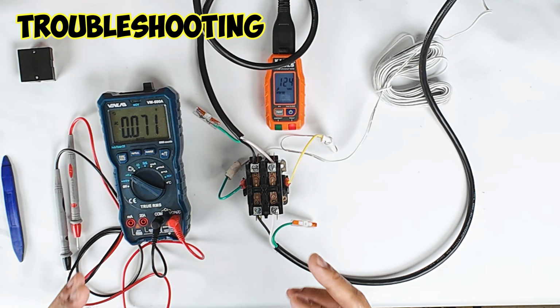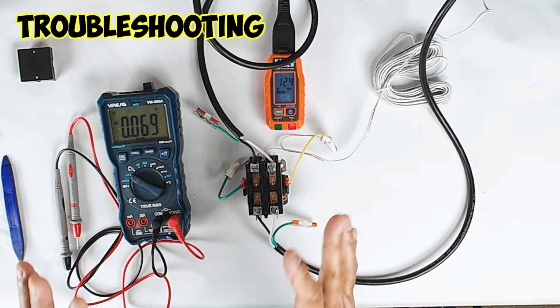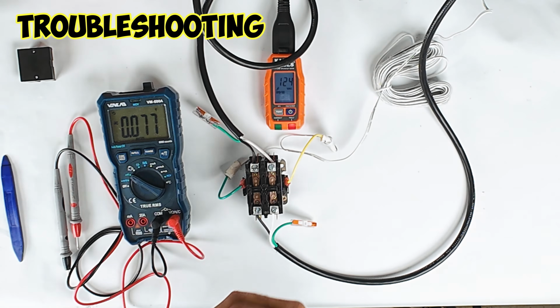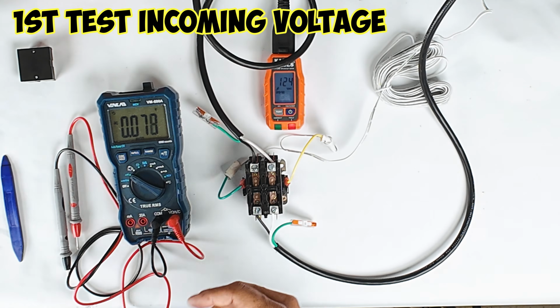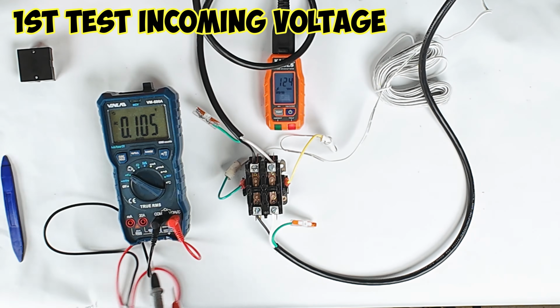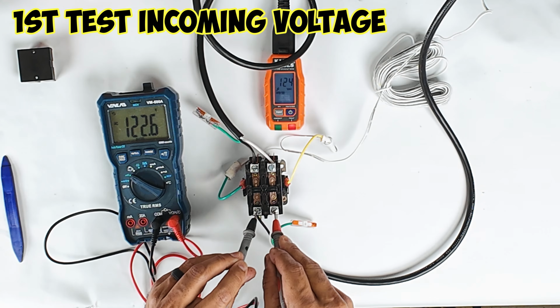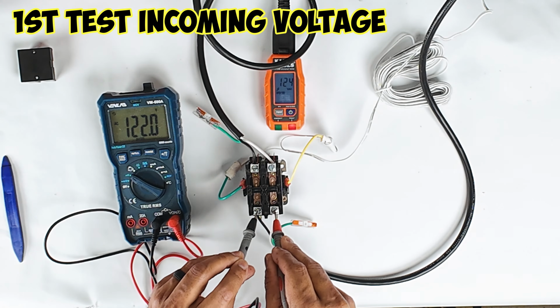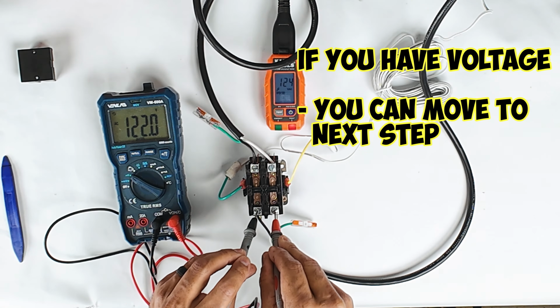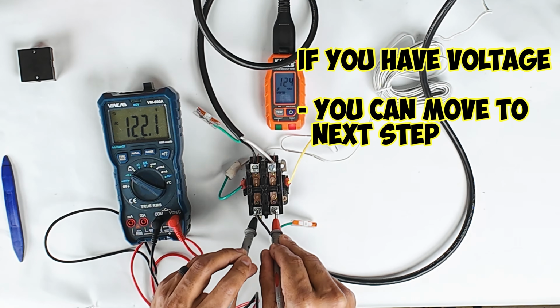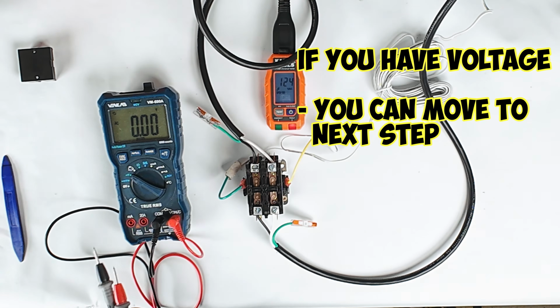All right, now that we've got the general gist of how this works, let's go ahead and talk about troubleshooting. Whenever you have issues with your condenser outside, you want to check these things first. The first thing you want to do is check your incoming voltage. You're going to place the meter at the bottom of your contactor where the lines come in from outside. If you have high voltage coming in, then you know that the first step is clear.